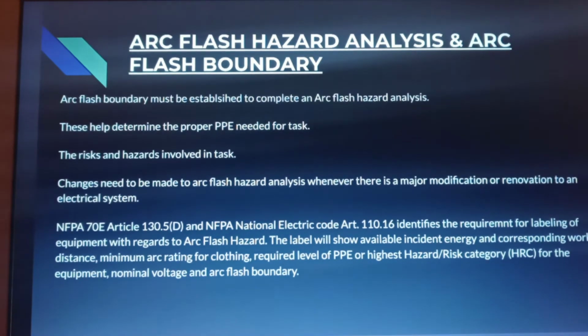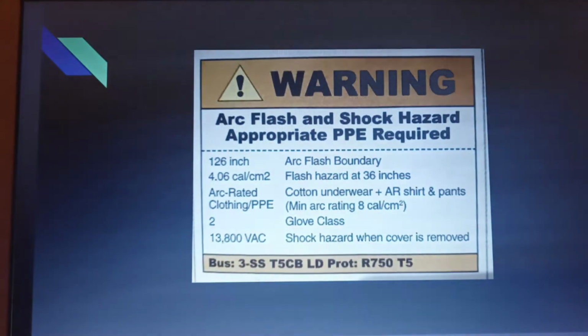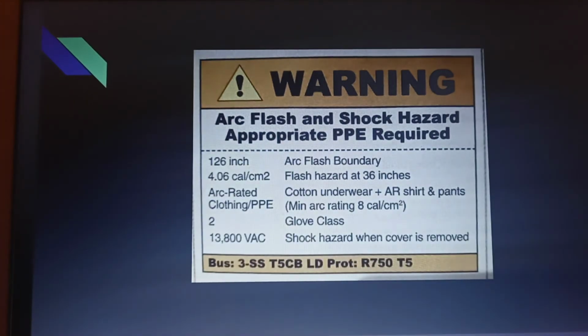And it says NFPA 70E Article 130.5D and NFPA National Electric Code Article 110.16 identifies the requirement for labeling of equipment with regards to arc flash hazard. The label will show available incident energy and corresponding working distances, minimum arc rating for clothing, required level of PPE or highest hazard/risk category for the equipment, the nominal voltage, and the arc flash boundaries. And then on the next slide is an example of that warning label.